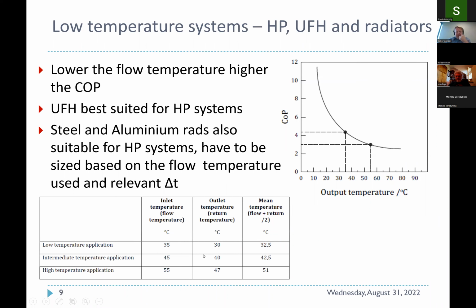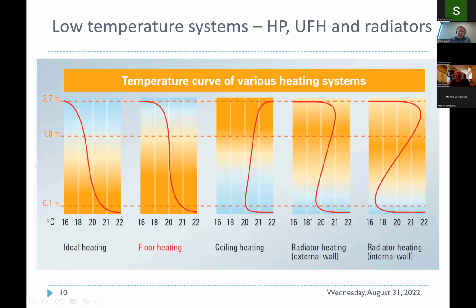So you will find that a lot of the times, for example, in a new home, people will be a little bit unsure about how to run or operate the system just because of the lower temperature in the radiator. It's always important, if you deal with somebody new to this, to let them know to check their thermostat and see what the actual room temperature is, never mind the flow temperature or the temperature of the radiator. I have put in a nice slide that will show the ideal heating scenario, typically the most comfortable way, where we achieve the best comfort at about 1.8 to 1.9 meters.